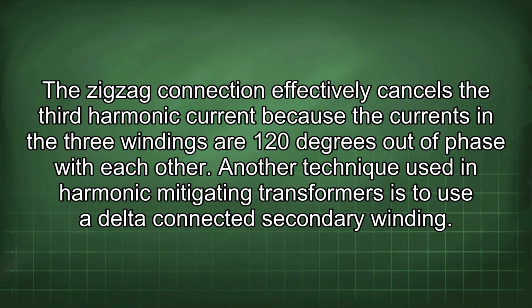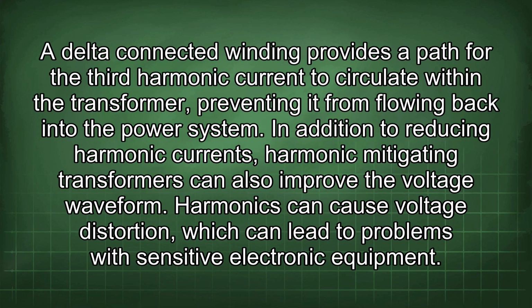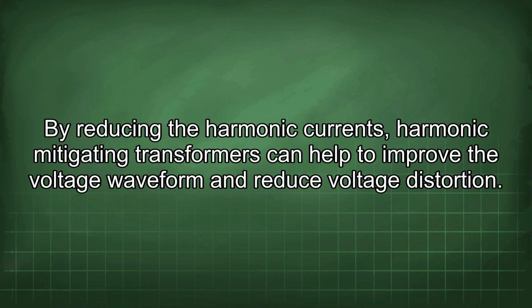Another technique used in harmonic mitigating transformers is to use a delta-connected secondary winding. A delta-connected winding provides a path for the third harmonic current to circulate within the transformer, preventing it from flowing back into the power system. In addition to reducing harmonic currents, harmonic mitigating transformers can also improve the voltage waveform. Harmonics can cause voltage distortion, which can lead to problems with sensitive electronic equipment. By reducing the harmonic currents, harmonic mitigating transformers can help to improve the voltage waveform and reduce voltage distortion.